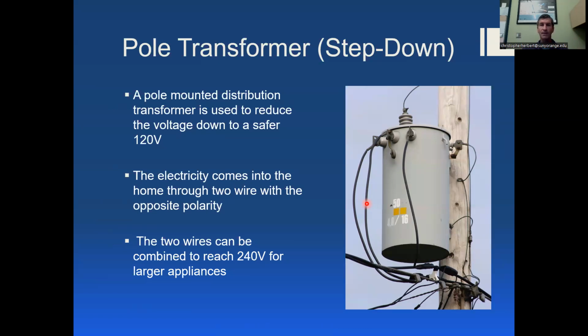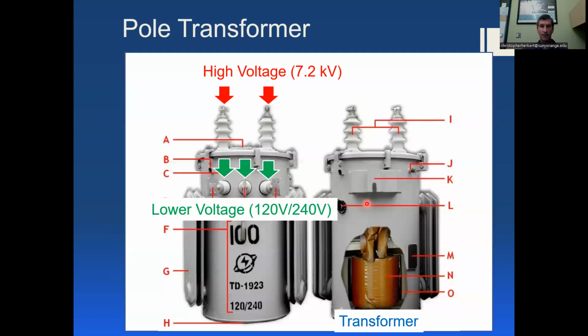And again, two hot leads, probably at 120 each, so that when you look at the taps on some of these, this tap would be at 120 volts, this tap would be at 120 volts compared to this neutral. And then this compared to this, because they're 180 degrees out of phase, would give you a total voltage of 240. So here's a transformer that sits in the bottom of one of these. These are your high voltage taps coming in at 7.2 kilovolts. And then our output connected to the secondary coils at 120 volts.